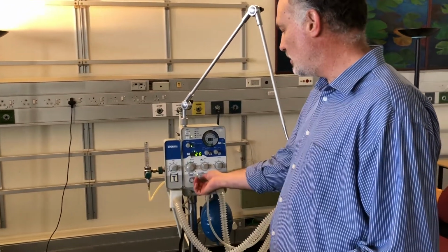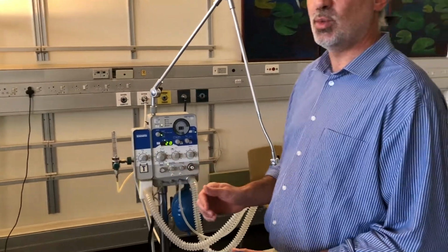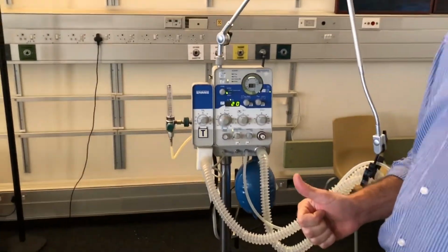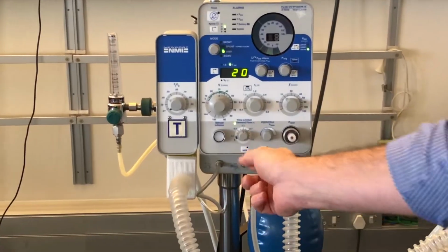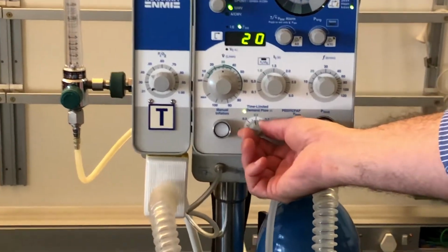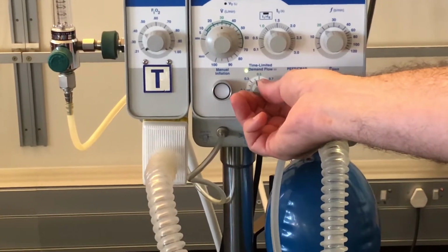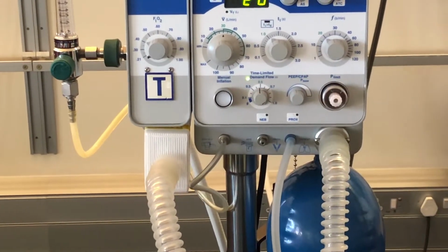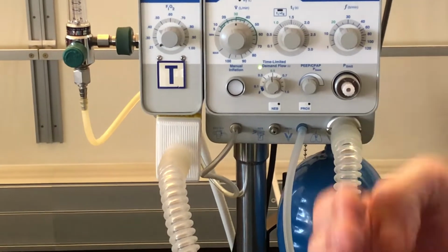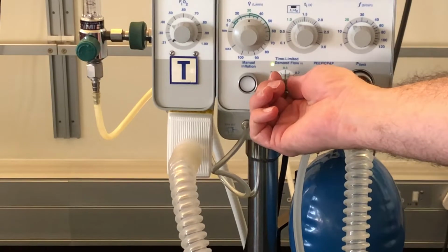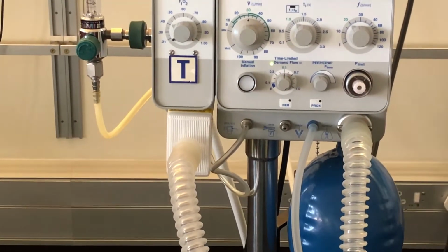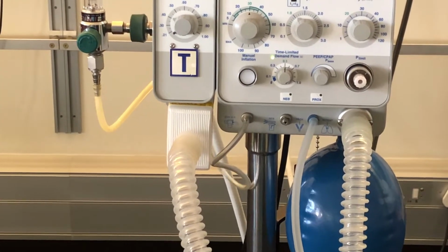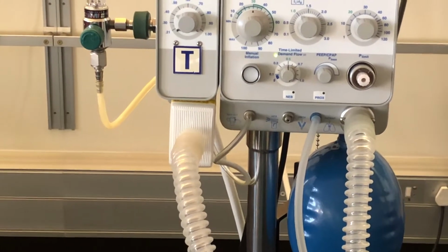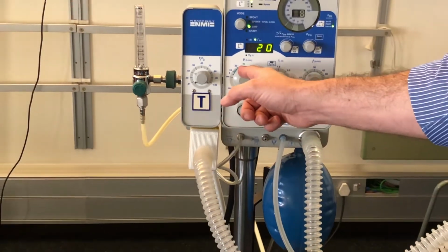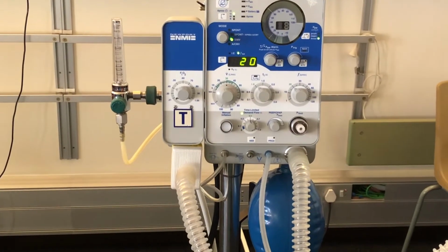So time-limited demand flow brings into it two issues. One is the time, and the second is the flow. So the actual setting that we have here is for an amount of time that we want the machine to make flow available to the patient. And you'll see that the green setting is a half a second. In other words, for the first half second of the patient's inspiratory effort, the machine will make a flow of gas available in terms of our preset flow rates.